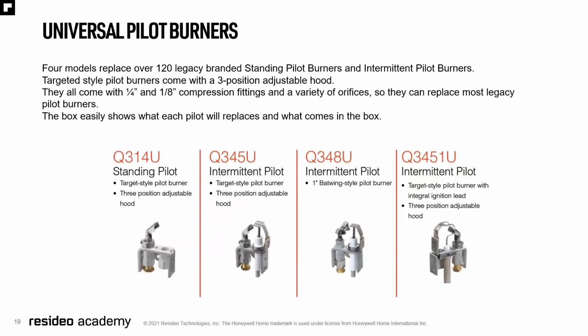The universal pilot burners. We now have 4 models that replace over 120 legacy branded standing pilot burners and intermittent pilot burners. They come with a 3-position adjustable hood. All the targeted ones do. Come with a 1/4 inch and 1/8 inch compression fitting and a variety of orifices so they can replace most legacy pilot burners. The box tells you which pilot comes in each box and what parts it comes with.